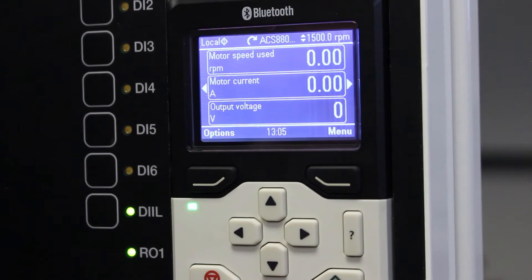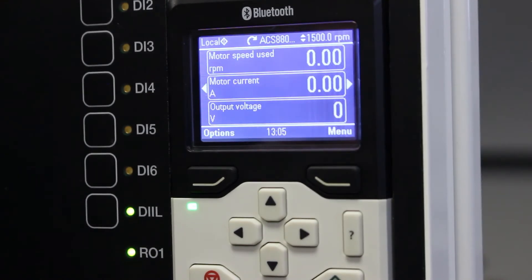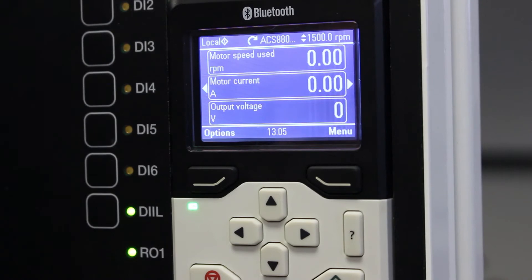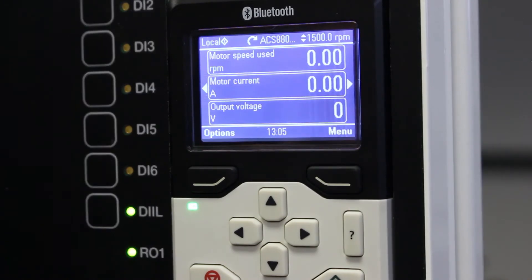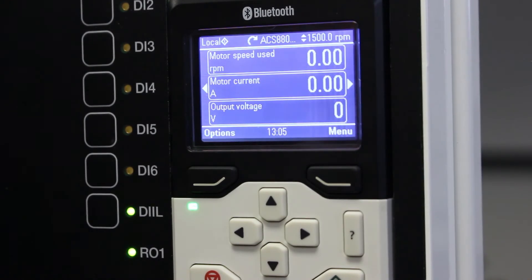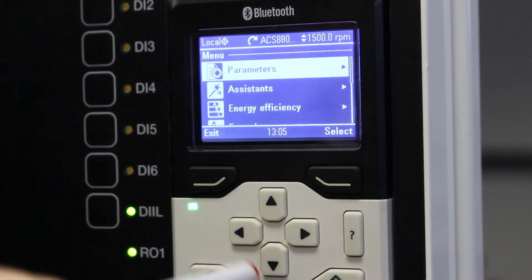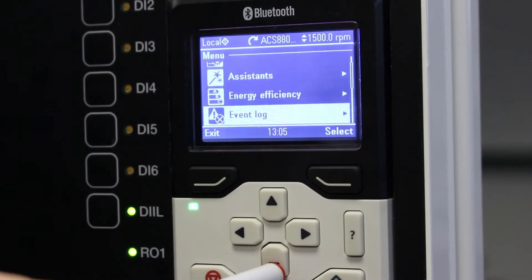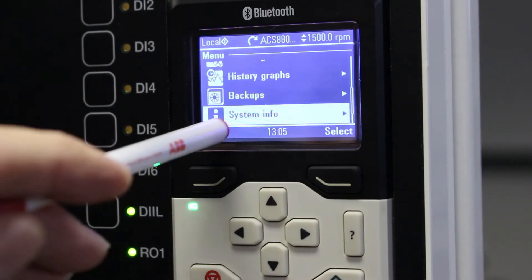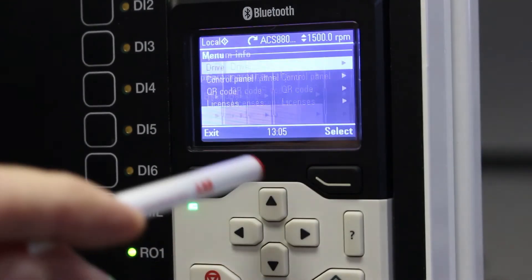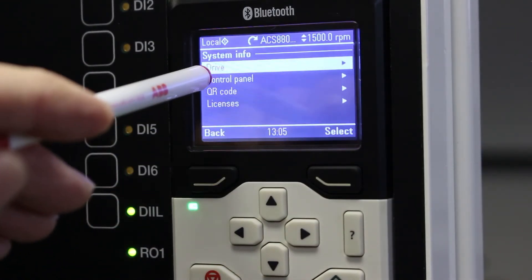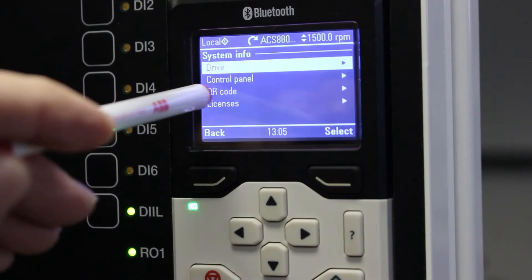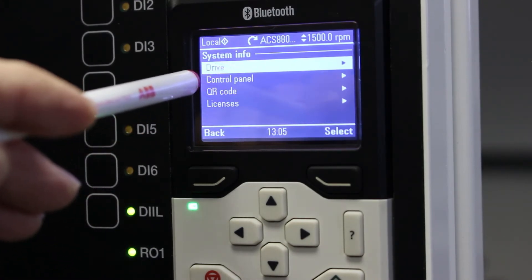If ABB service engineer requests the firmware version, whether it's for the VSD itself or for the control panel, just go to menu, scroll down until you see system info. Select it and there you will see system info for the drive, system info for the control panel.